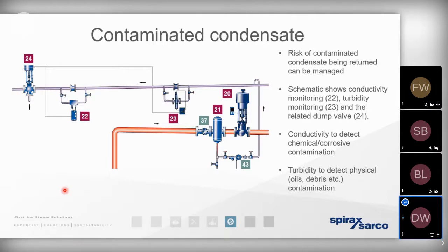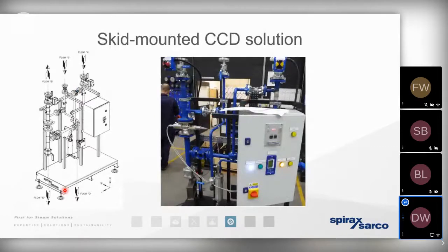But there's an opportunity here to recover it when it is in an excellent condition. The reason being, if we can move towards a turbidity or a conductivity probe that could sit a run of pipework ahead of a diverting valve, well, it can dump contaminated condensate to waste when it's not in a condition to be reused. But when it is in a good condition, we can make use of that hot water by bringing it back to the boiler house. And even if that condensate is being dumped to waste, then maybe it can be put to waste across a very simple heat recovery solution. So contamination control devices can either be mounted in line, or for larger solutions, they can be skid mounted. It basically comes down to recognizing the value that that condensate has as hot water.